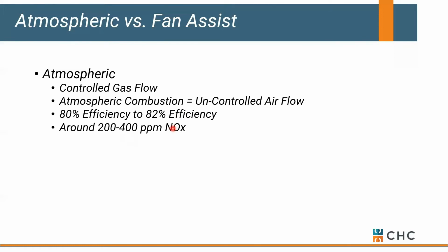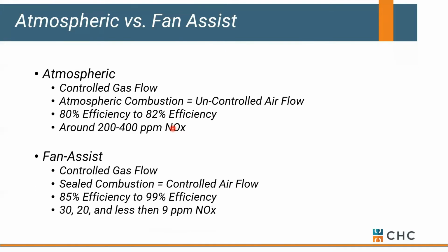Okay. So what do we do to get around that? We put a fan on it. We put a fan on our boiler. Most boilers that you're going to see, the majority out in the marketplace, you can call them fan assist. They simply have a fan that allows us to control both the airflow and the gas flow, and improves our efficiency numbers. Okay, so we can be much friendlier to the environment if we're burning natural gas.